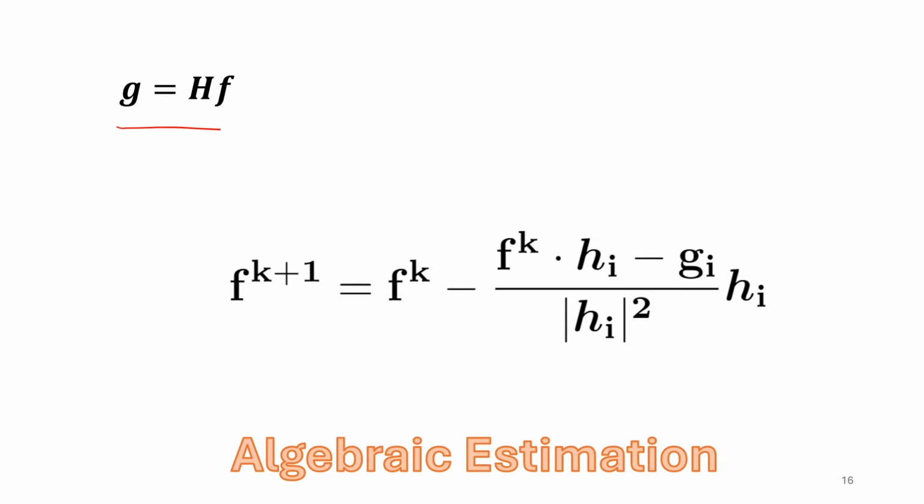These iterative algorithms operate row by row. This is what's called simultaneous algebraic reconstruction. It's a popular reconstruction algorithm. It takes each component of H, each vector in H, and then tries to make the estimate of the object consistent with that single vector in the H matrix.